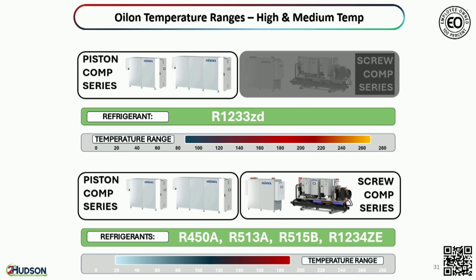For the Oilon heat pumps, for temperatures below 190, so all of these are high temperature, we have everything, and pretty much all A1s to start. Oilon does offer A2Ls, and they do offer butane and propane for the European markets, but in New York we're really pushing just A1s. So you have 450, 513, 1234, 515B. What you pick really depends on what you consider important: are you really capacity focused, are you at a certain temperature predominantly over another, or are you really concerned with your emissions? Because you might be willing to sacrifice some COP or capacity in order to get a better GWP or a better ozone depletion.